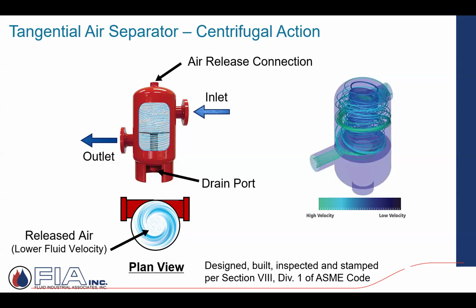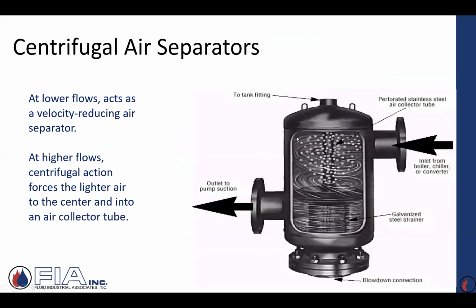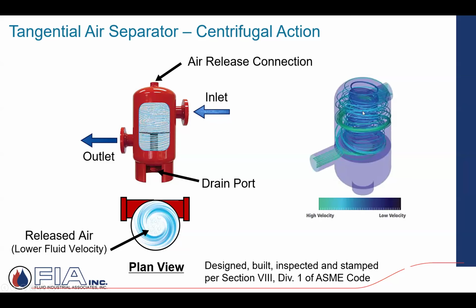The air is lighter, the water's heavier. The water's going to get thrown to the outer edges of this shell. The lighter air collects in the interior, and they'll have a collector tube, they call it a stainless steel air collector tube, internally here. And so the lighter air gathers in the center, and the heavier water that's separating from the air discharges out the discharge nozzle, air free. Now I'm going into a suction of a pump, perfect. Now I'm going up to the building, air free, perfect. That's what I'm trying to achieve here.